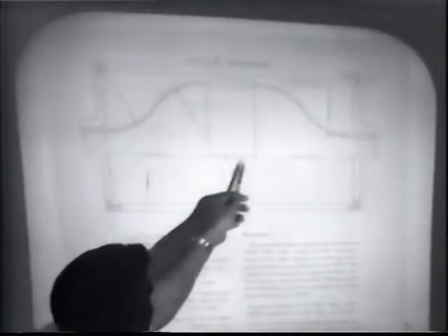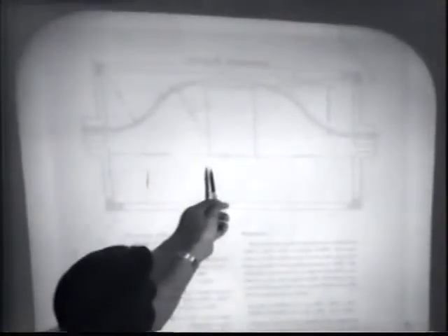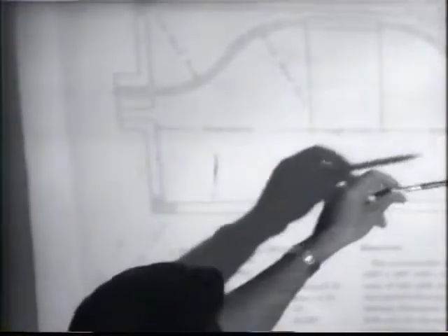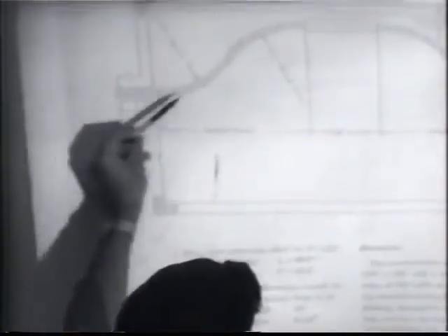You can look at those later on, but it's essentially based on the length of the joint for splicing, and then with some given radius. In other words, the cable is entering here and leaving there, and so we need some radius to train the cable around to the wall for splicing, and also that allows for expansion and contraction in the cable due to heating and cooling cycles that it has.